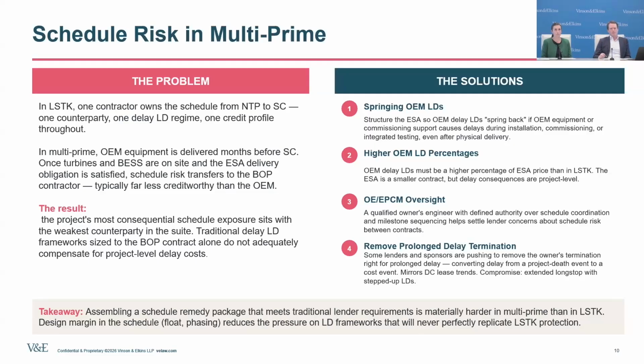Now I want to get into more detail on the schedule risk problem in multi-prime contracting. As we've said, lump sum turnkey is easy, you have a single point of responsibility. Once you have 3 or 4 major equipment packages and 2 or 3 different contractors operating on site, it becomes a much muddier picture. There are various things you can do to manage this. You can't eliminate the risk that one contractor does something with a rippling effect through all the other contracts, and that your recourse against that contractor isn't adequate. But you can certainly give yourself the best chance of having recourse if that happens.